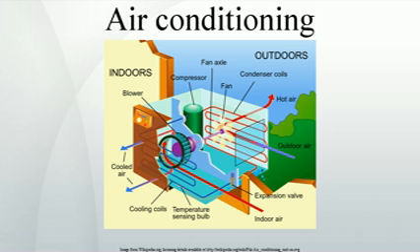Portable units. A portable air conditioner is one on wheels that can be easily transported inside a home or office. They are currently available with capacities of about 5,000 to 60,000 British thermal units per hour, 1,800 to 18,000 W output, and with and without electric resistance heaters. Portable air conditioners are either evaporative or refrigerative. Portable refrigerative air conditioners come in two forms, split and hose.